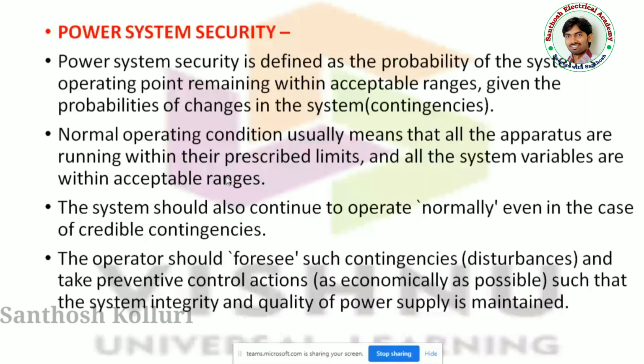That means because of that contingency, the system may not lose its security. The system may not lose its security is called credible contingency. The surge will be there for a few seconds, then it will automatically disappear. So that can be called credible contingencies. The system should also continue to operate normally, even in the case of credible contingencies. So this is also a very important point while you design the relay operation.